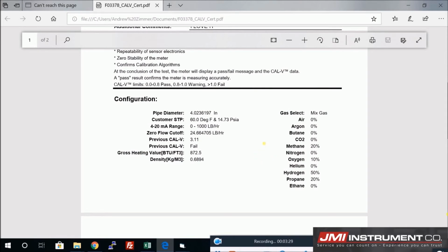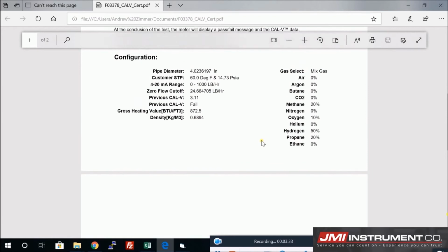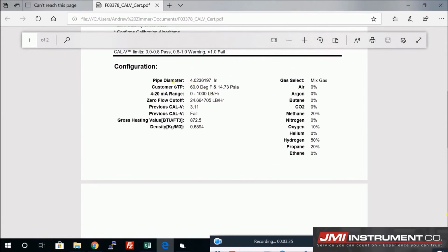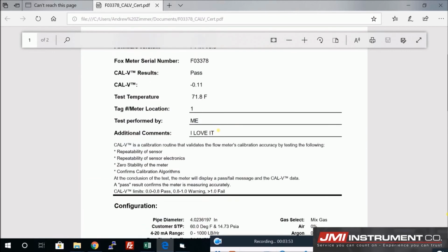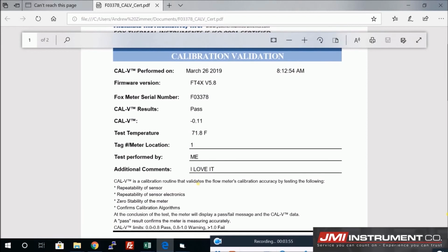It confirms when the previous Cal-V value was. You see here configuration. This is our imaginary configuration: pipe diameter, temperature, pressures. All of this is changeable in the software, FT4X View. And here is gas select. This is the gas that we had in the pipe. And there we have it. So that is a calibration validation. It validates the flow meter's calibration accuracy by testing all these things back to the NIST traceable standard.